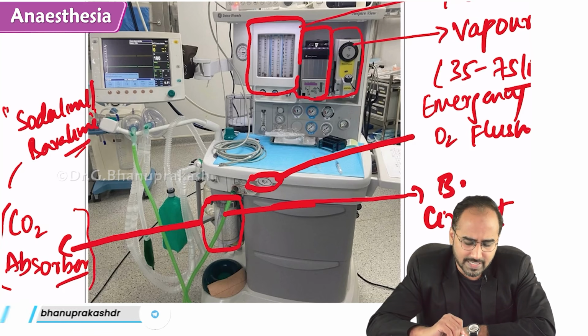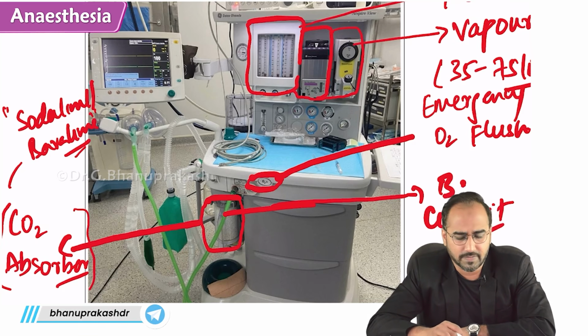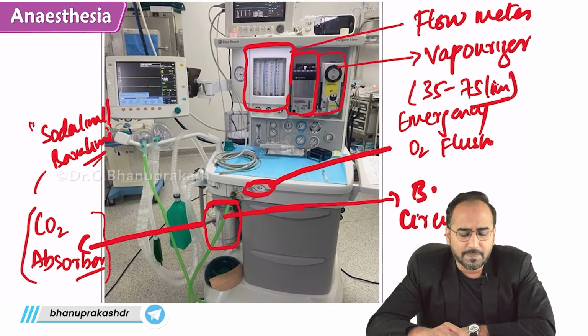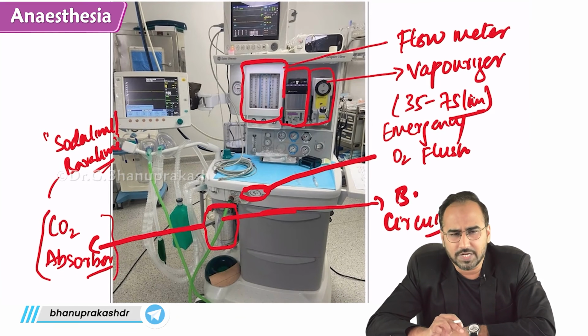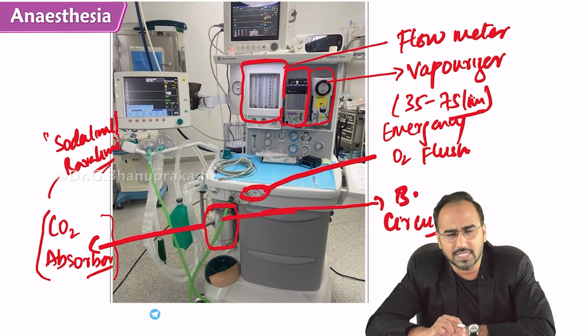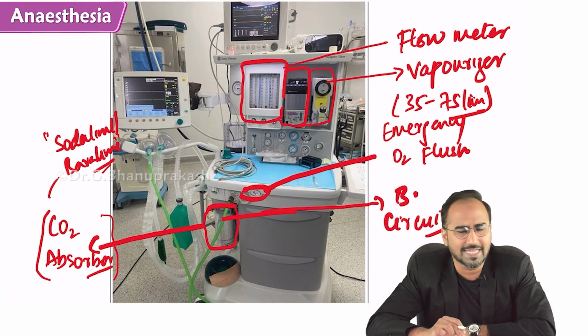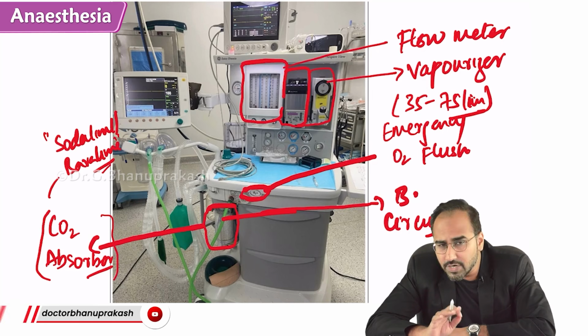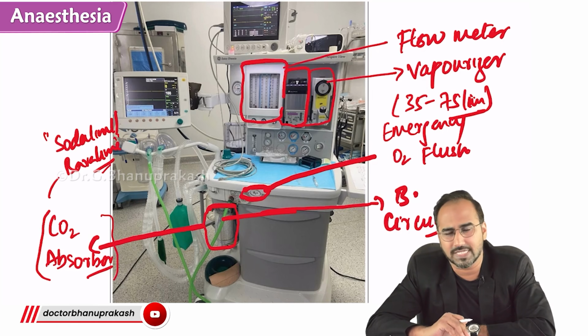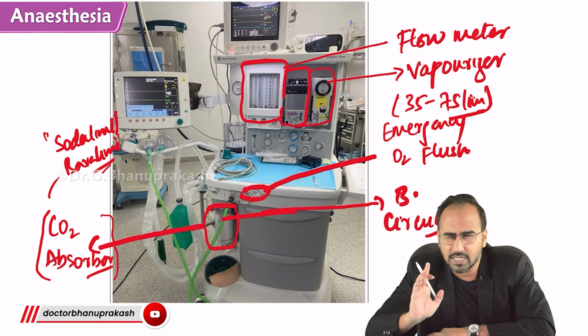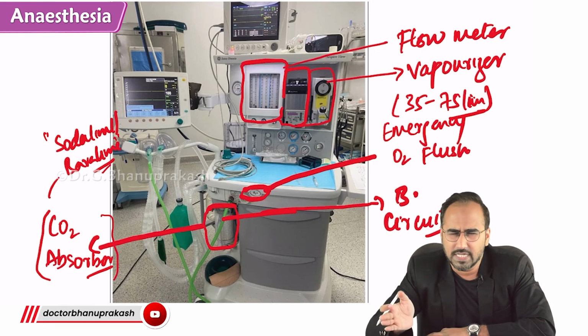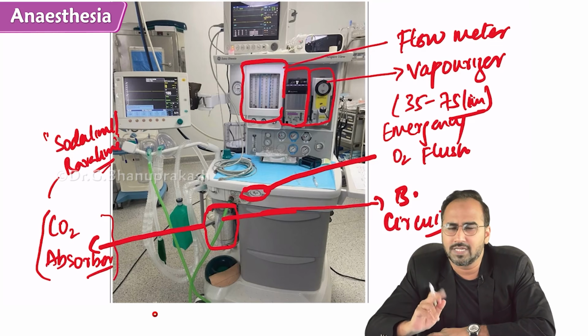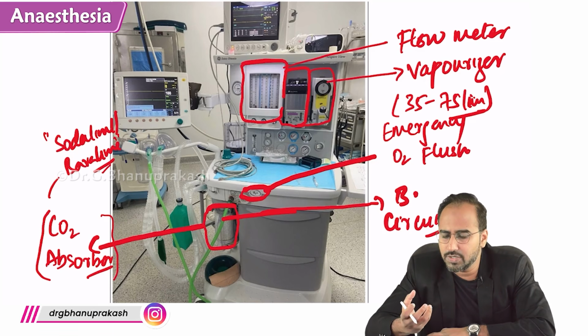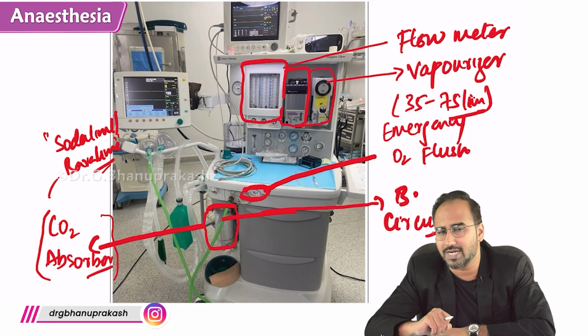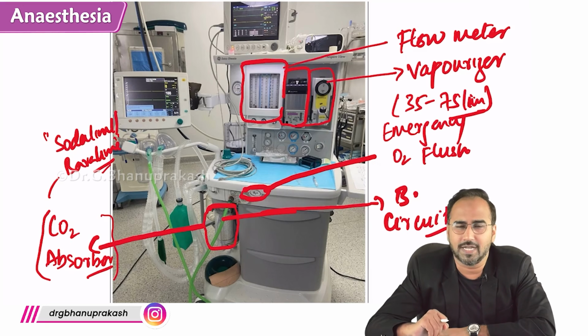So this was regarding the parts of the machine. Once again, guys, have a picture memory. First of all, what is this machine? This is called Boyle's machine, introduced by Edmund Gaskin Boyle in the year 1917. The function of Boyle's machine is to reduce the pressure of the gas to an acceptable limit. The first part is the cylinder. The cylinder is attached to the machine with the help of a steel assembly. What is this steel assembly called? The yoke valve assembly. Inside the yoke valve assembly, you will see a system that prevents wrong attachment. What is that system? The pin index system.